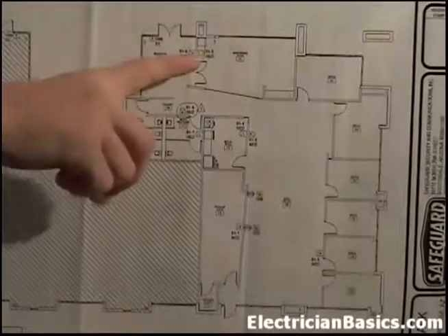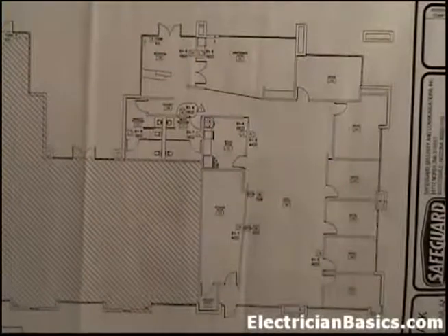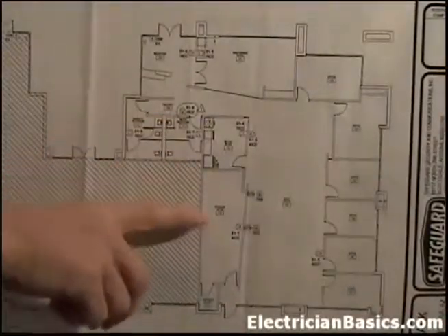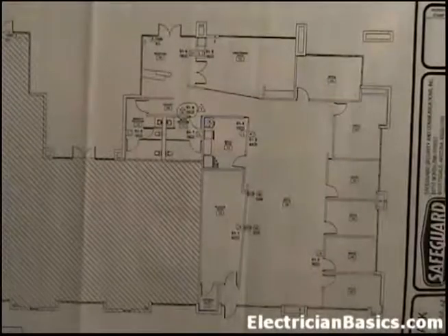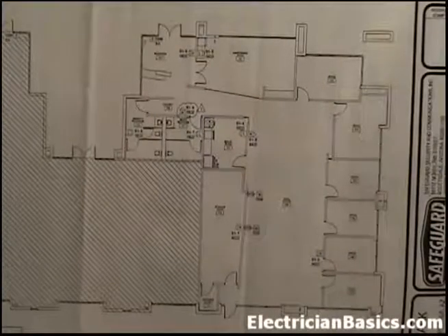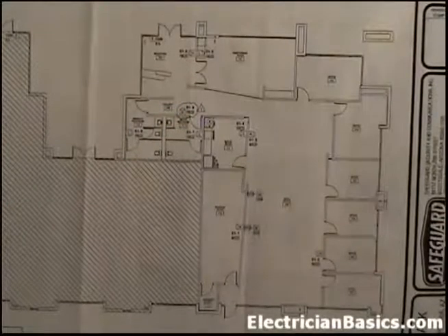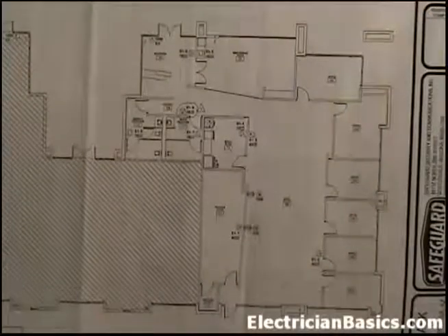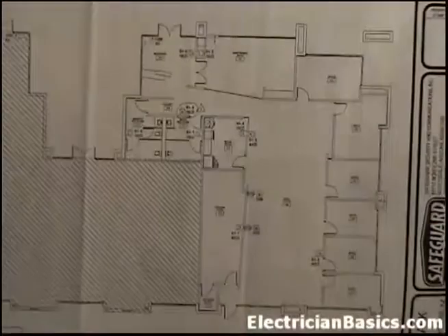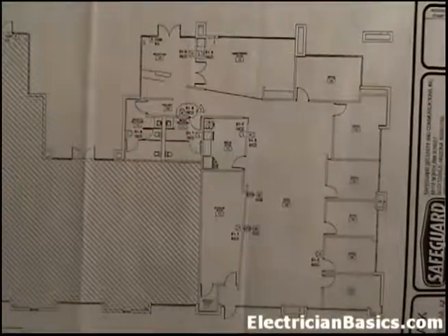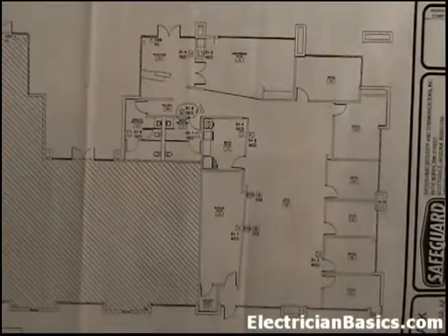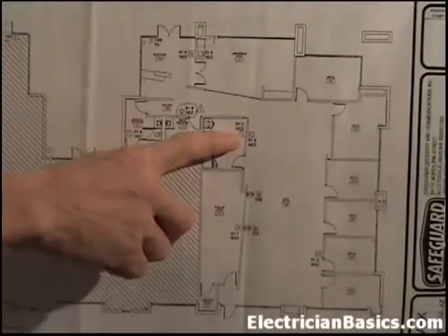So it has to go from here back to the riser room into the NACPS panel. And once again, we want to mention it has to be in a separate conduit. You can't have a junction box in here where they both meet and it goes back and comes back in the same panel. It has to be a separate conduit that goes back from the last device all the way back to the NACPS panel. What you need to do is go from device to device and see how this must be looped. Now you must build it this way in this sequence, because the monitor is going to be computer operated and these devices are addressable.